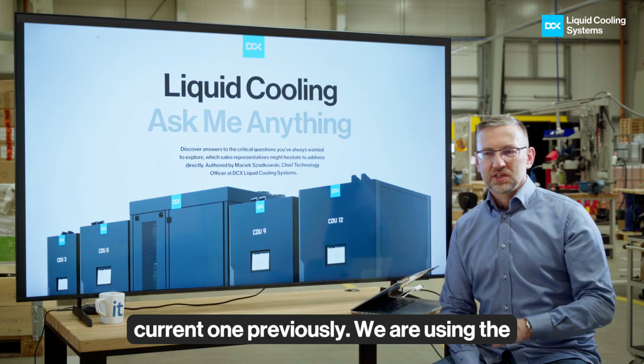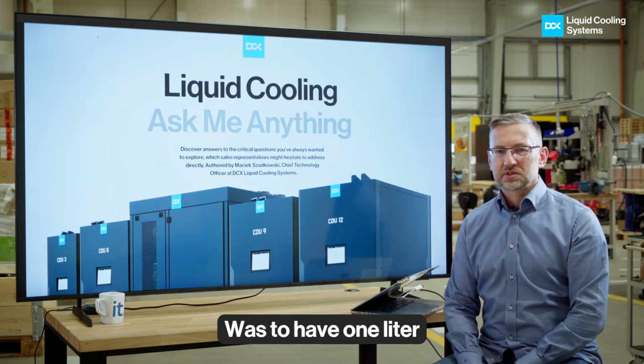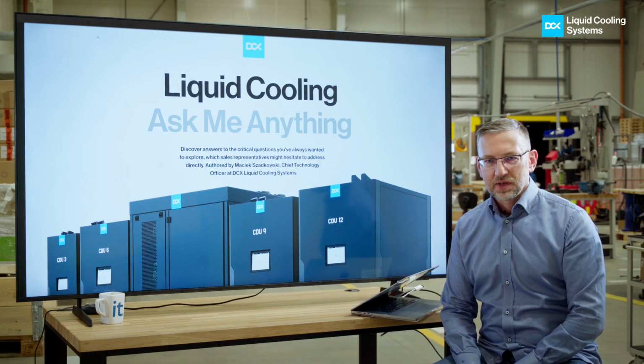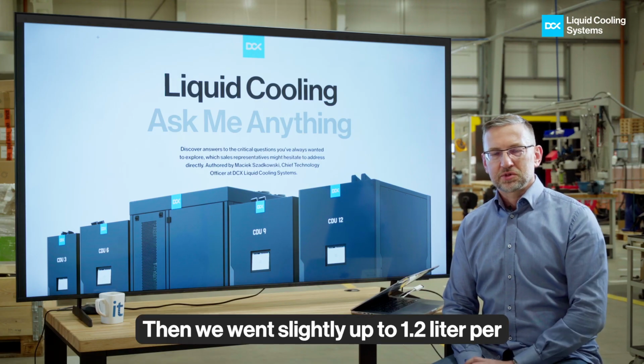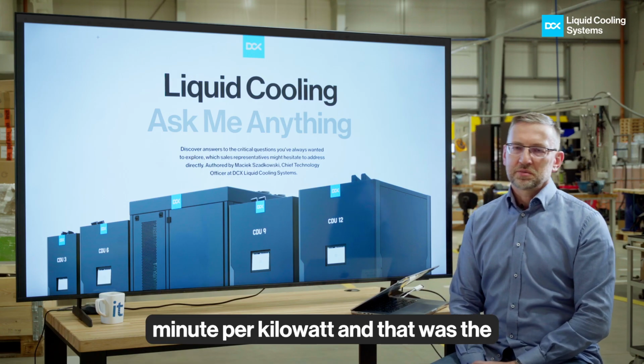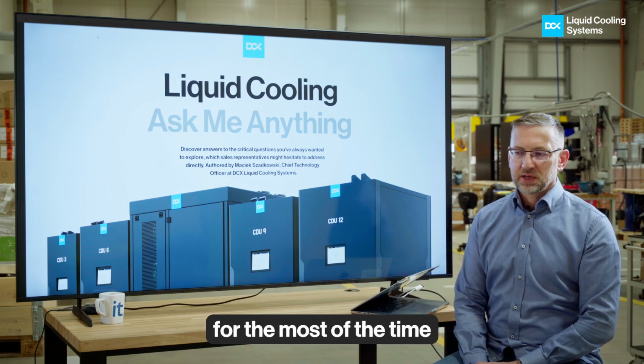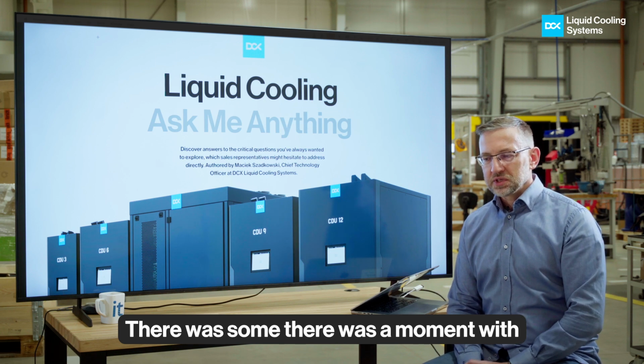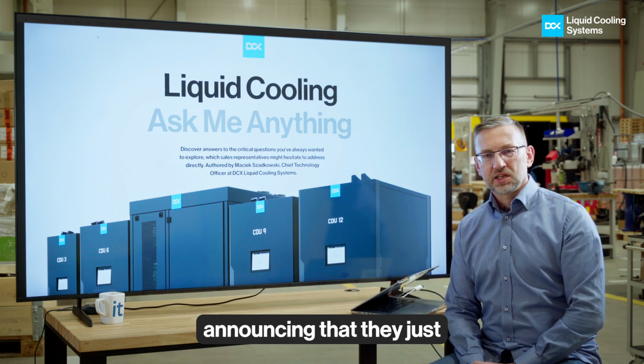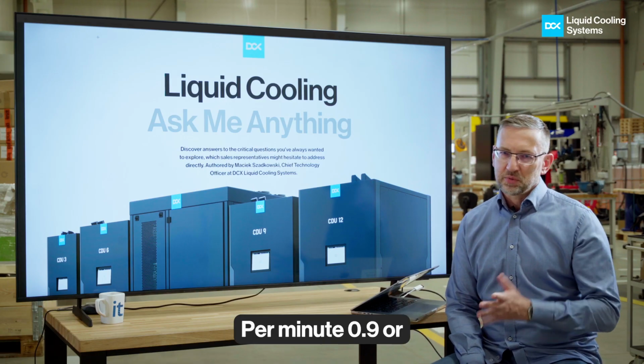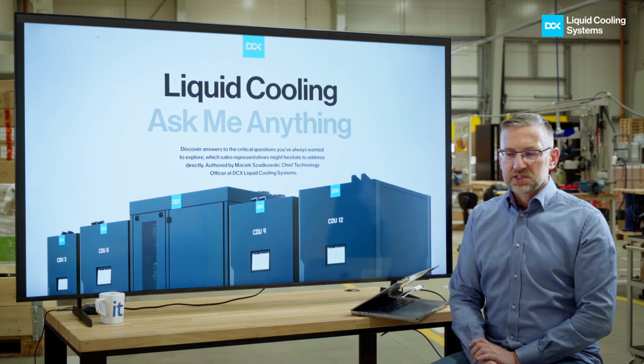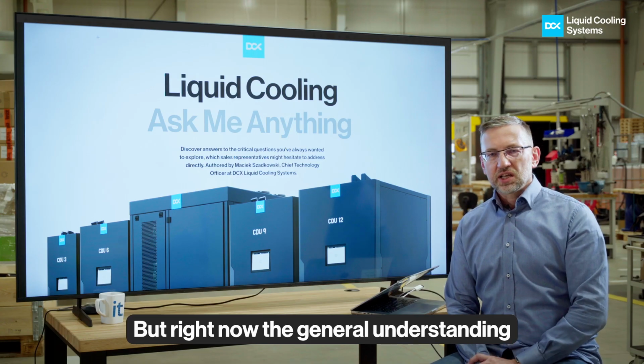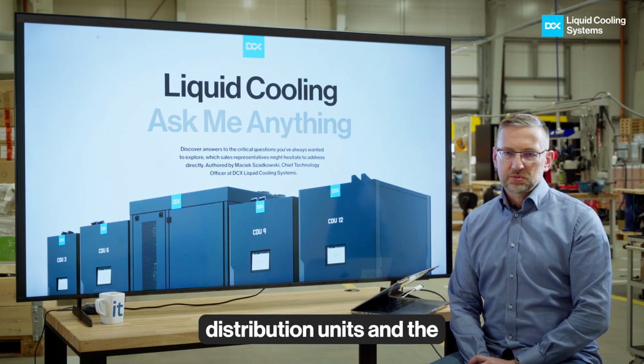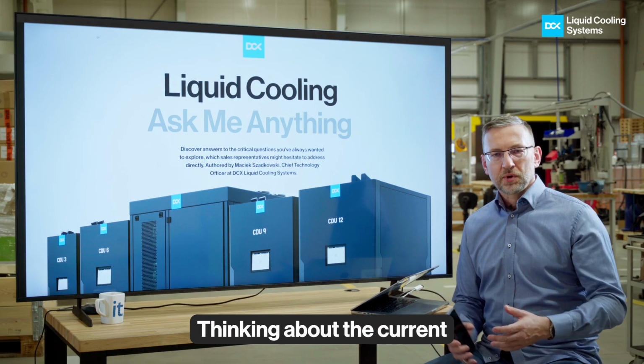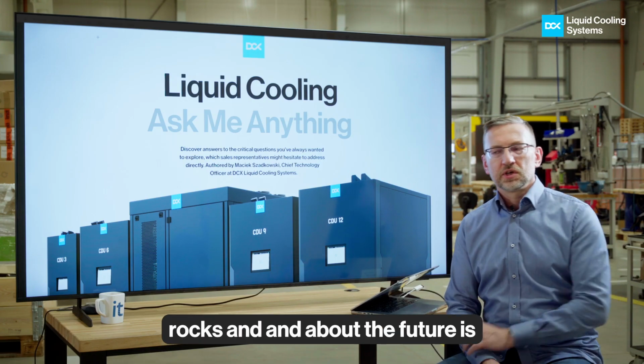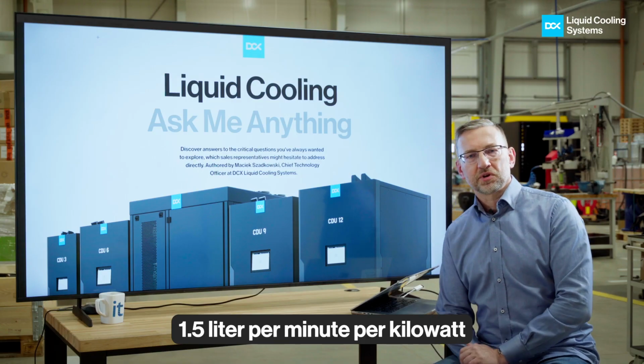Previously, the general understanding was to have 1 liter per minute per kilowatt. Then we went slightly up to 1.2 liters per minute per kilowatt, and that was the understanding for most of the time. At the beginning of the year, NVIDIA announced that they need less than 1 liter per minute, 0.9 or something like that, for those racks. But right now, the general understanding, when thinking about coolant distribution units and the flow rate you would assume for the current racks and for the future, is 1.5 liters per minute per kilowatt.